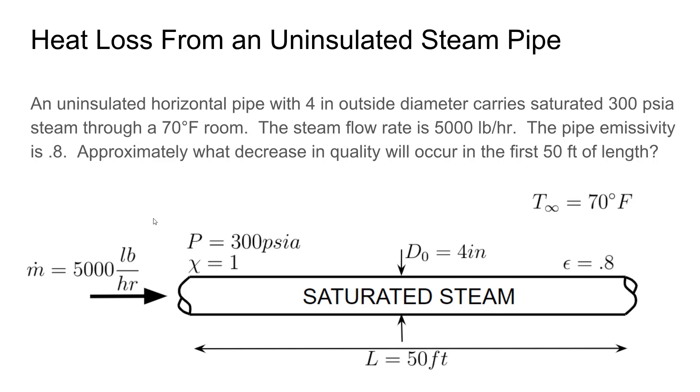We know the outside diameter of the pipe is 4 inches, and we only care about the heat loss in the first 50 feet of length. We know the ambient temperature of the room is 70 degrees, and we've been given the emissivity of the pipe, which is an important clue that the heat loss may be driven not only by convection, but also by radiation. We know there's no conduction since the pipe is not in direct contact with anything other than the surrounding air.